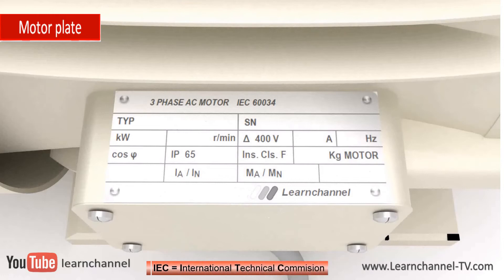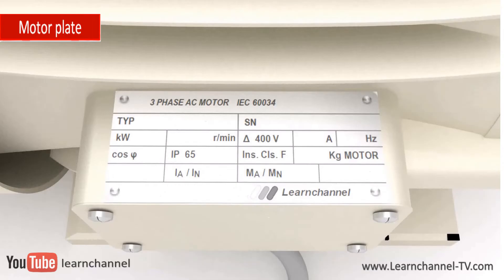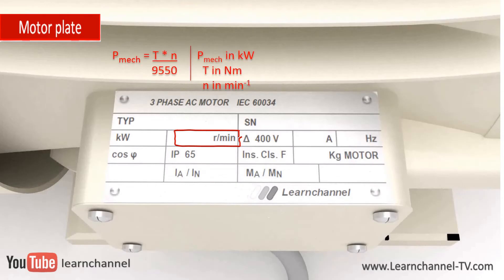In the next section, we discuss the basic information given by the nameplate. The International Electrotechnical Commission established standards for the information provided on the nameplate. The motor's rated mechanical output power is given in kilowatts. Motor rated speed, or full-load RPM, is the approximate RPM at which the rotor is rotating when the motor is operating under full load. With the information of the mechanical power and the rated speed, you can calculate the rated torque by this equation.